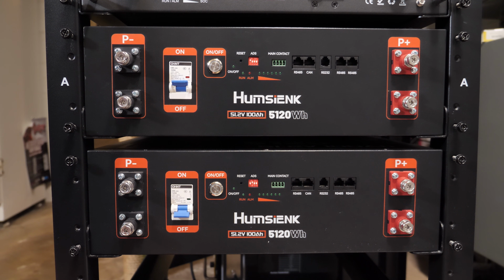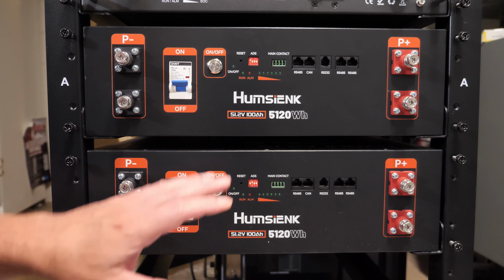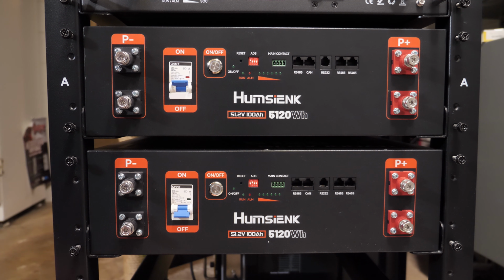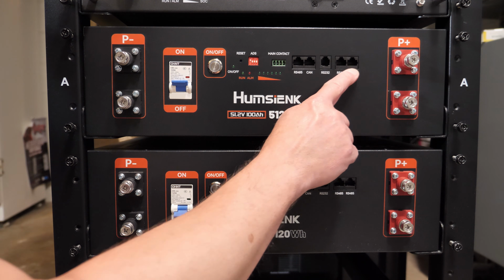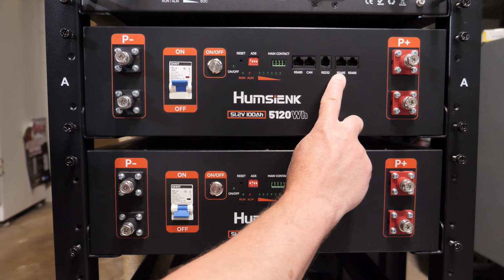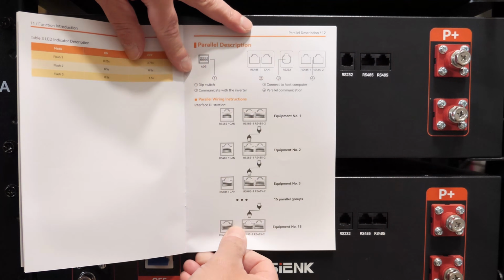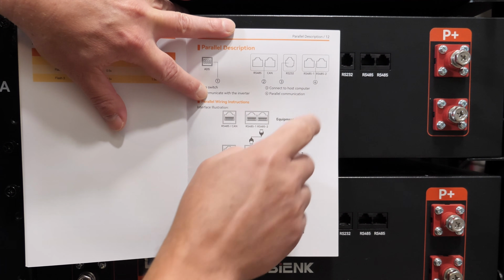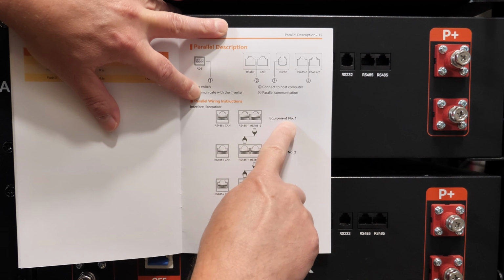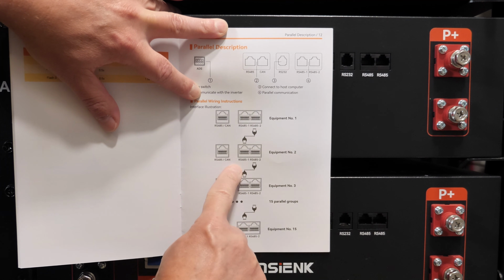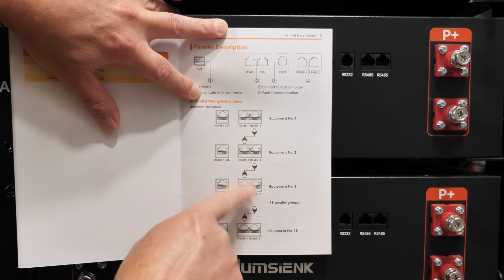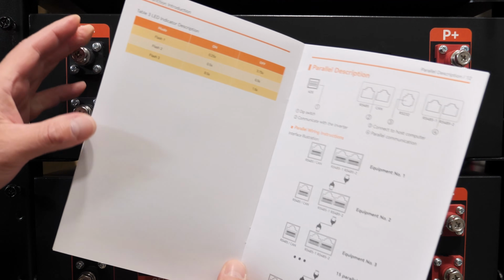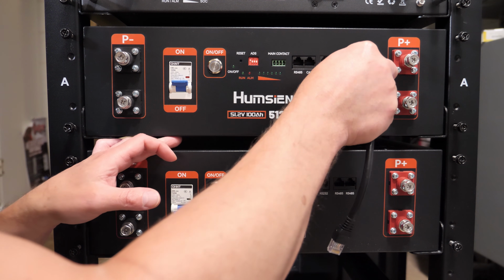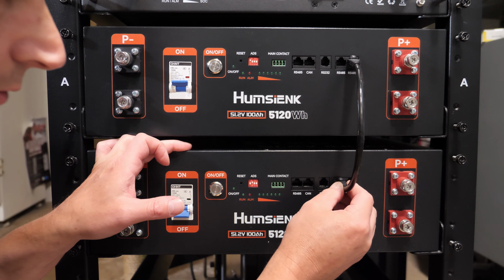Step number 3, the battery directly connected to the inverter should be set as the master battery, again, which will be this one right here, while the other ones will be slave units. Step number 4, communication between batteries should be connected using the 485 out to 485 in. So that is these 2 ports right here. In the manual, it shows this one as being in and this one being out, which I can show you. So if we take a look right here, there's our 2 485 ports. If you look at the pictures right here for equipment number 1, or battery number 1, we're going to go to the out, to the in of the next battery, and so forth if you have a bunch of batteries connected together. All right, so we will go ahead and do that now for battery number 1 going to out, battery number 2 going to in.